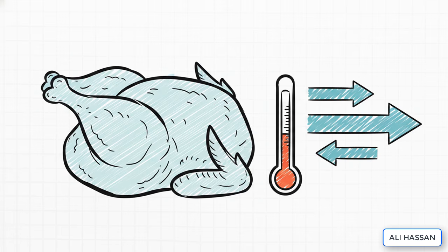Let's go back to our 225 tons of chicken for a second. Even if it shows up frozen, it might not be at the final target temperature of minus 18 degrees Celsius. So all the energy needed to pull that remaining heat out of the chicken itself, that's called the product load. And believe it or not, it can often be the single biggest factor in the entire calculation.